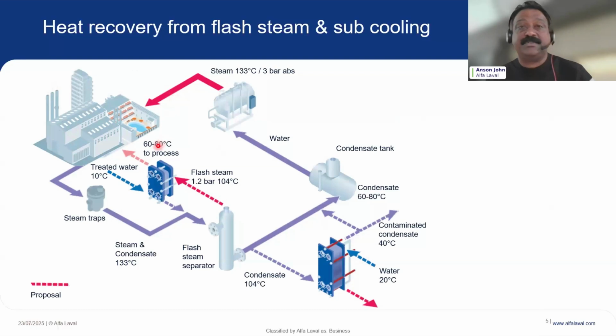The other thing is heat recovery from flash steam and subcooling. You can see here, you can do a lot of heat recovery from the flash steam, which is at 104 degrees C or 1.2 bar pressure. You can easily heat up tap water from 10 degrees to 60 to 80 degrees C, depending on your application. And this is getting pretty popular. We are working closely with different companies, engineering companies, to do this. I have not done a return on investment calculation here because it really varies, but we have seen that the return on investment is close to 2 years, slightly more or less, depending on the application. So it's pretty interesting.